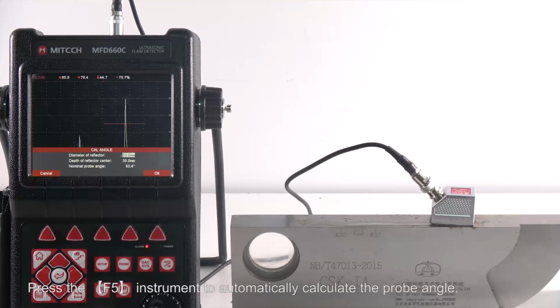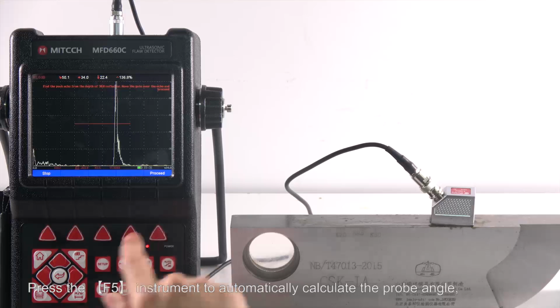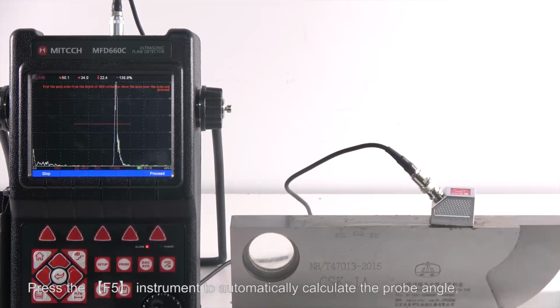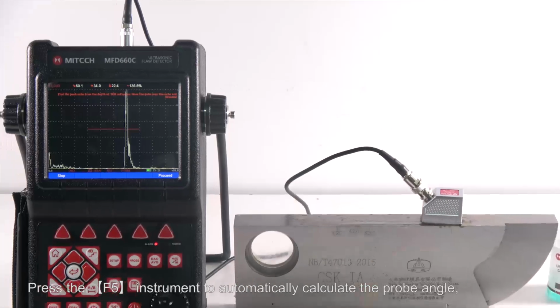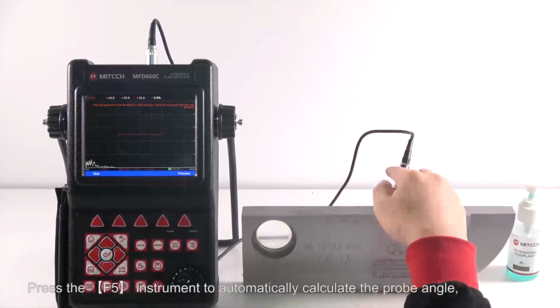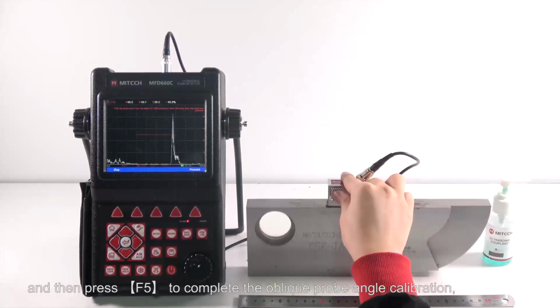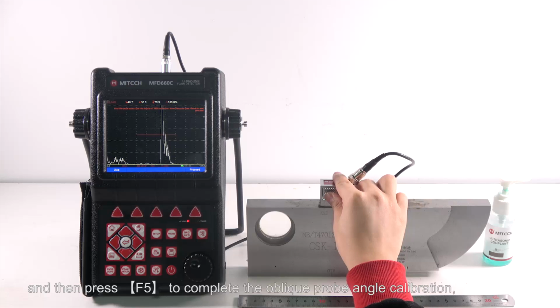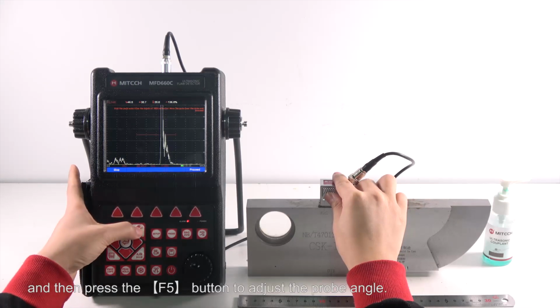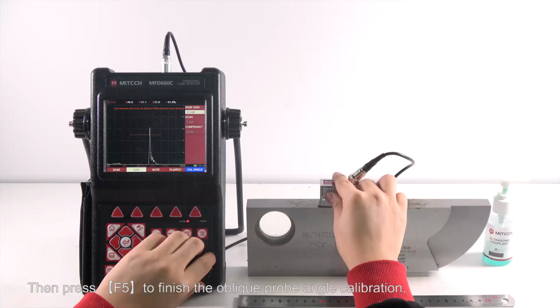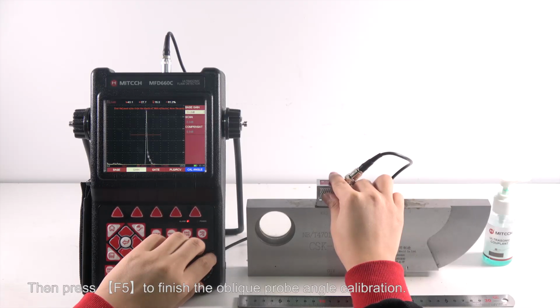Press F5 and the instrument automatically calculates the probe angle. Then press F5 to adjust the probe angle. Then press F5 to finish the oblique probe angle calibration.